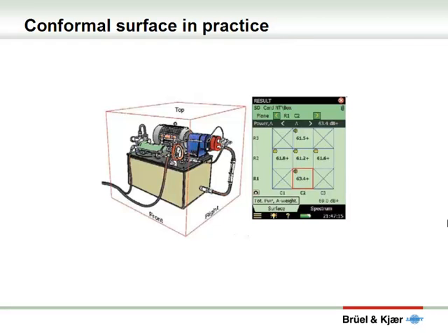Here is what it would look like in practice. The machine to be measured is enclosed by a measurement box consisting of five sides. And on the right, on the sound level meter screen, you will see this five-sided box flattened out into five surfaces, enabling the measurement to be done.